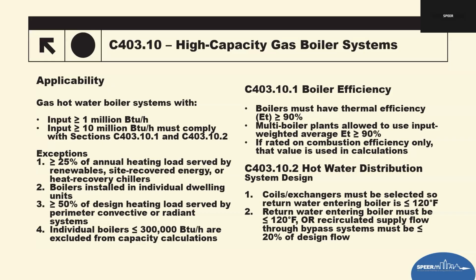Heat exchangers must be sized so that the design load water coming back to the boiler is 120 degrees or less. Under all operating conditions, either the return water entering the boiler stays 120 or less, or flow through a bypass piping, like a 3-way valve, must be less than or equal to 20% of the design, preventing hot water returning from the bypass system and degrading the performance. So these requirements help ensure condensing boilers operate efficiently and full performance is maintained during part load.